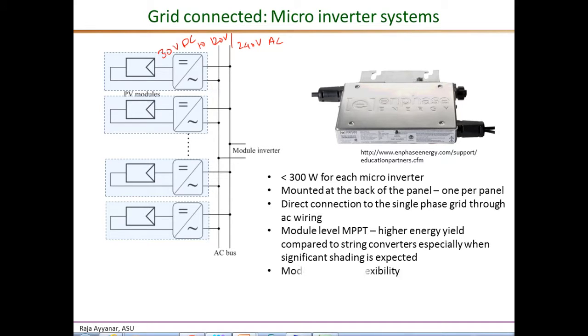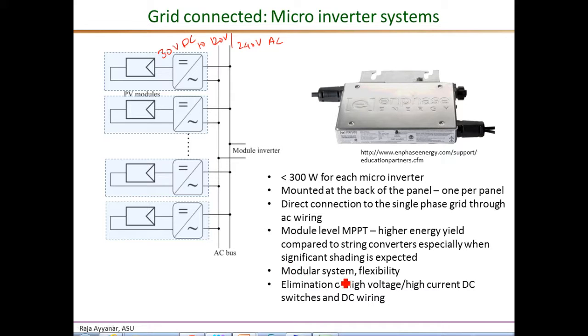Another advantage is that high-voltage, high-current DC wiring and DC switches are completely eliminated. The system is also inherently modular and flexible — if you want to increase the power rating, say from 3 kilowatts to 5 kilowatts, you simply add more panels with their built-in micro-inverters rather than reconfiguring DC wiring as would be needed with a string inverter. The main disadvantages are that micro-inverters tend to be more expensive on a per-watt basis compared to string inverters and certainly compared to central inverters, and their efficiency is currently one to three percent less than string inverters.